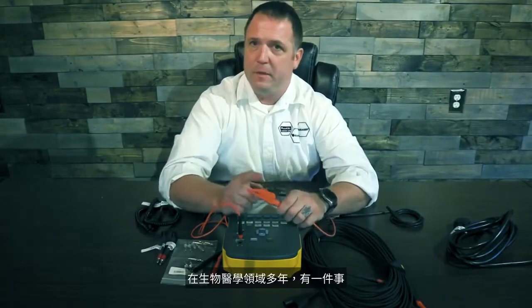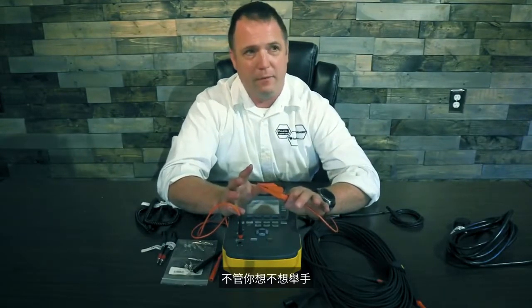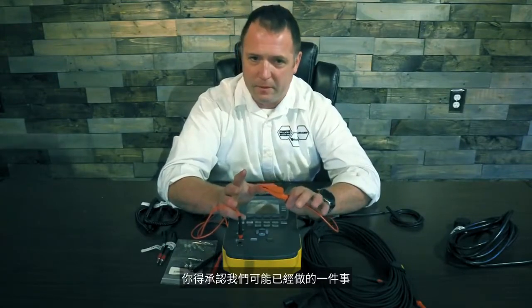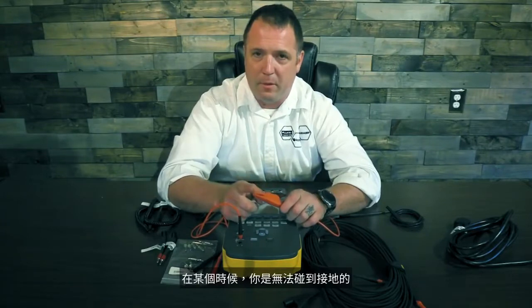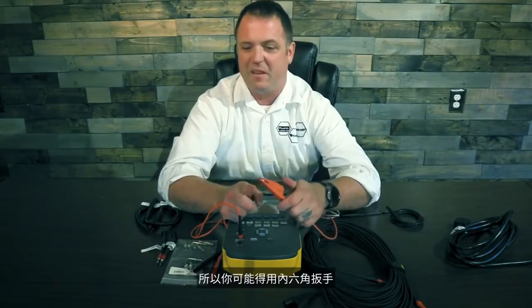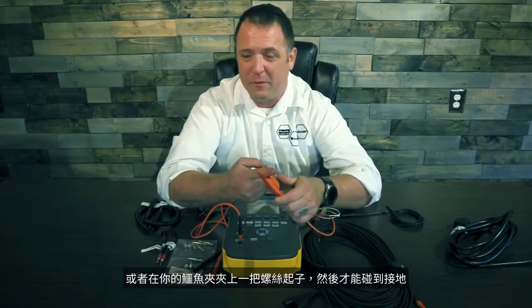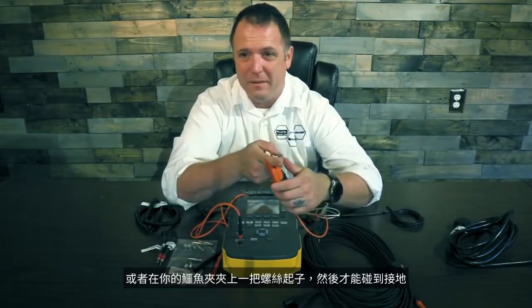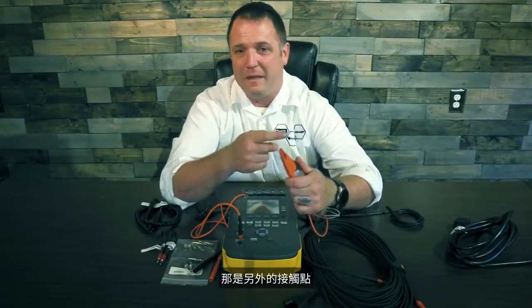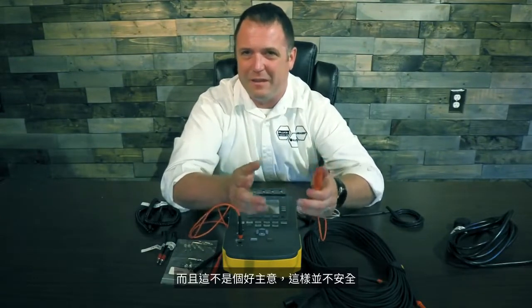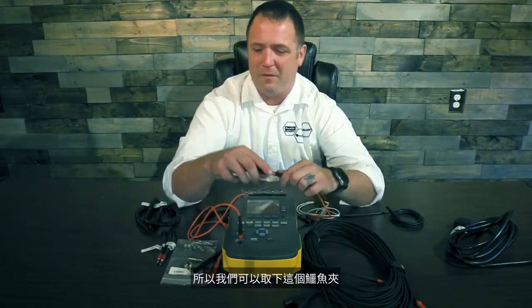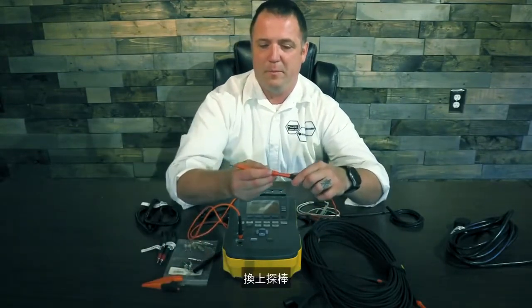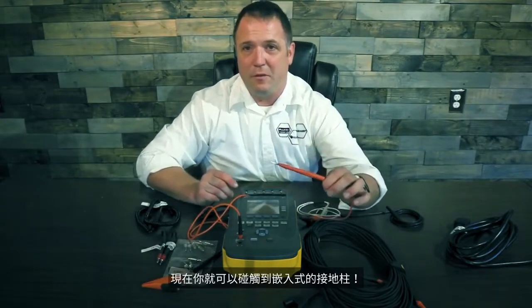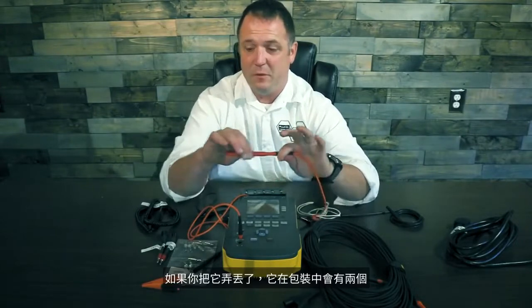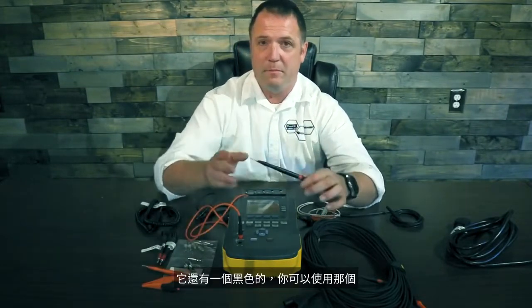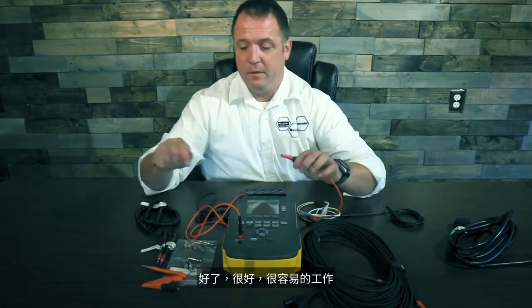All right, now here's something that I did as a biomed for years, and if you'd like to raise your hand or not, you have to admit that we've probably done it. At some point in time, you couldn't get to the ground part. You had to try to reach in through something, so you probably stuck an Allen wrench or a screwdriver in your alligator clip to reach in. That's another point of contact. It can change your resistances, and it's just not a good idea. It's not safe. So instead, we can take off this alligator clip and plug in the probe. That's simple, and now you can reach into those recessed ground pins. Nice and easy. If you lose it, it comes with two. It comes with the black one. You can use that one. There you go. Nice, easy trade out.